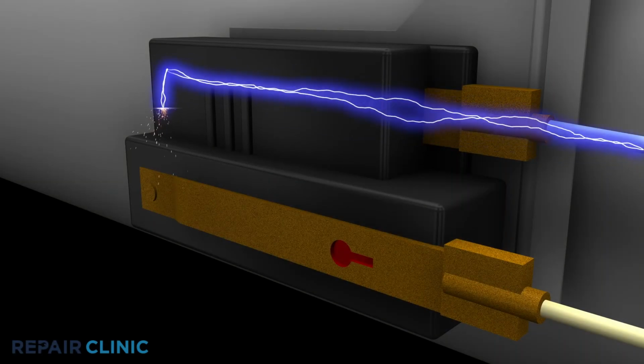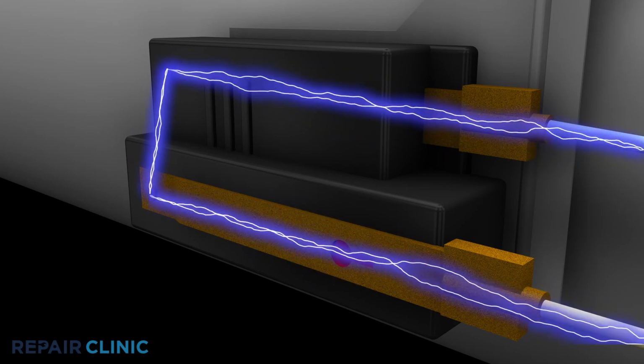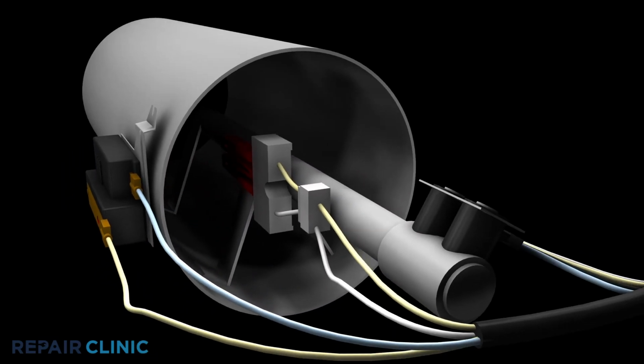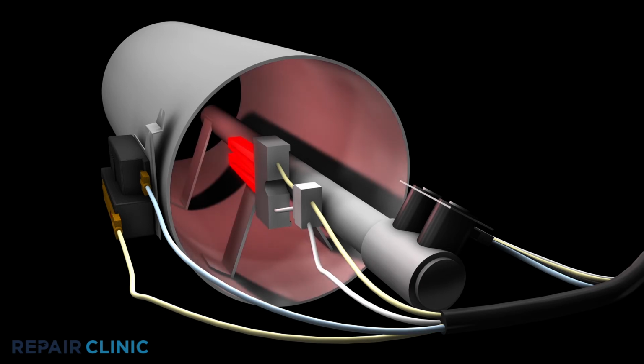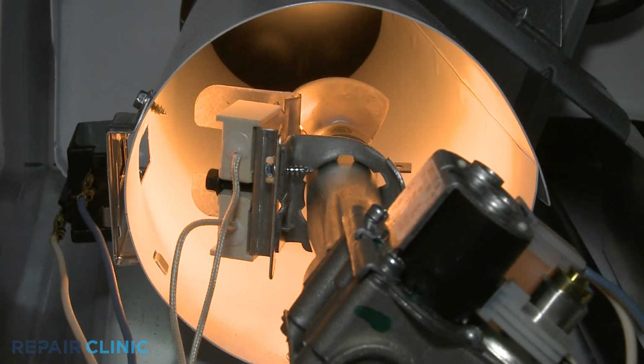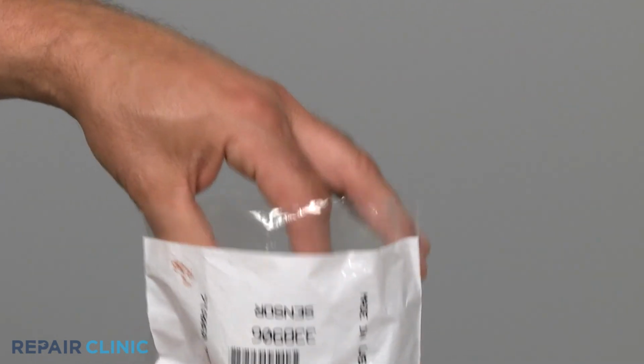Keep in mind that the flame sensor could potentially short out, which would still allow the igniter to glow, but would prevent voltage from reaching the gas valve coils. In this case, the igniter will glow but not turn off, and the flame will not be established. Again, the faulty flame sensor will need to be replaced.